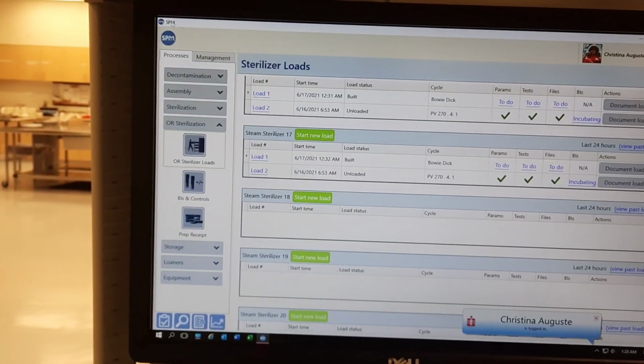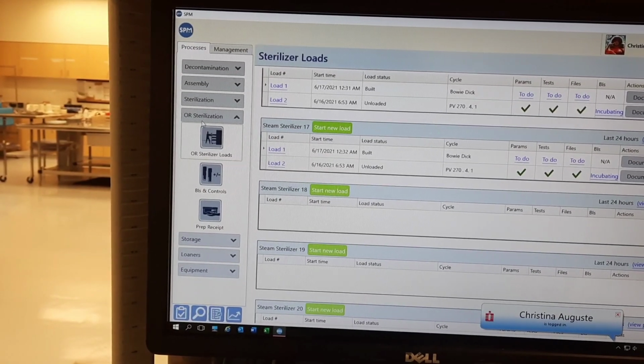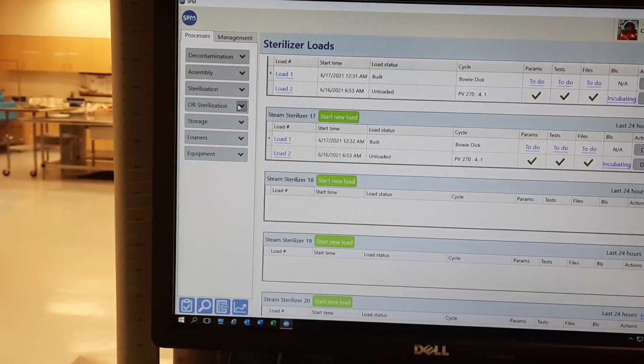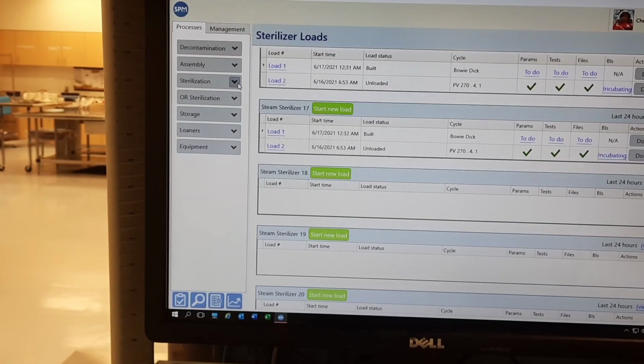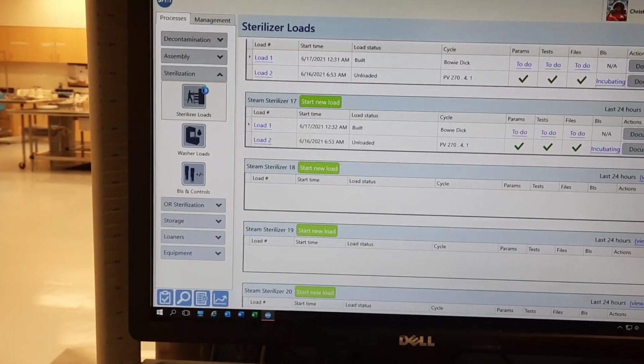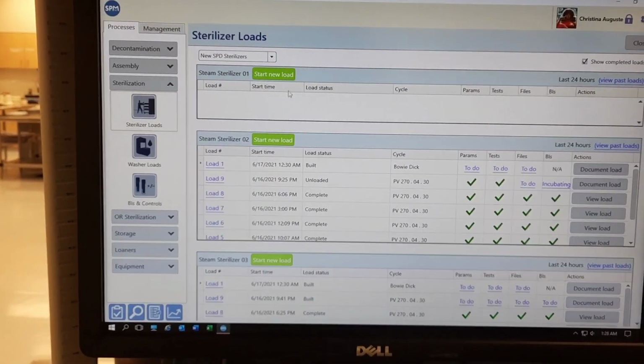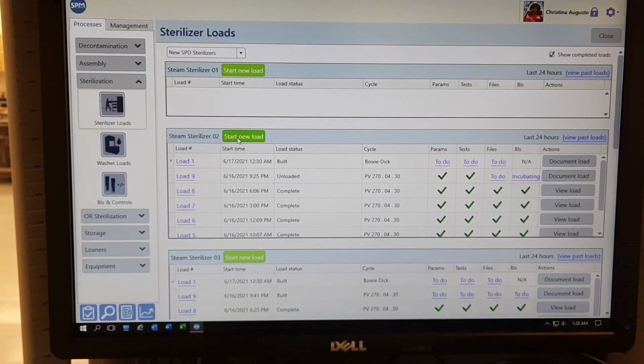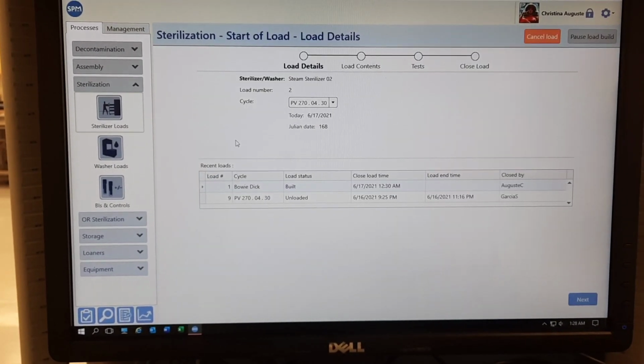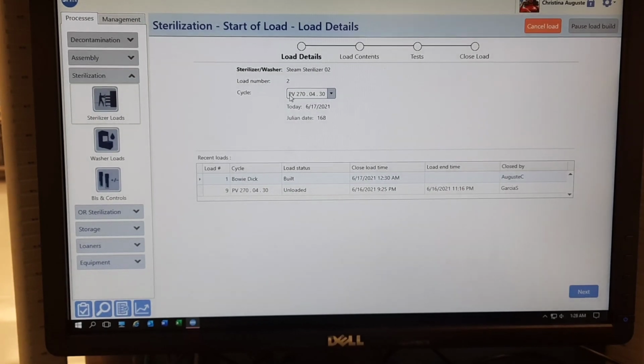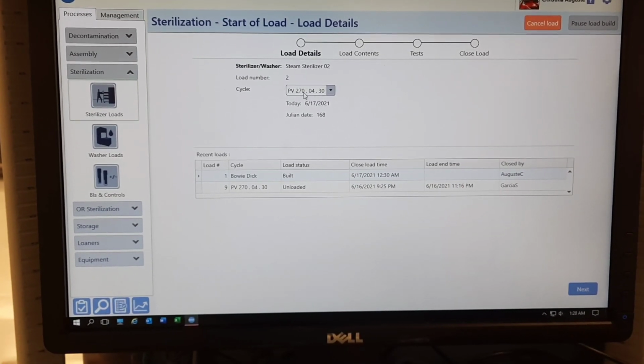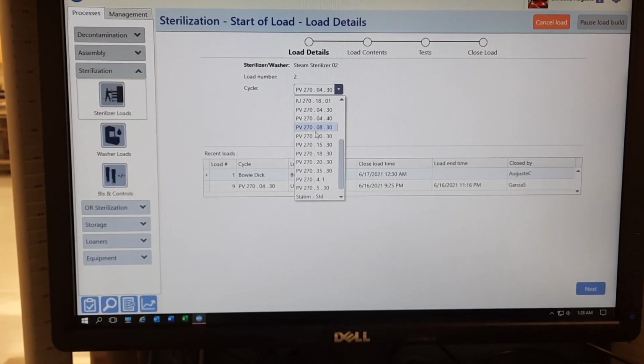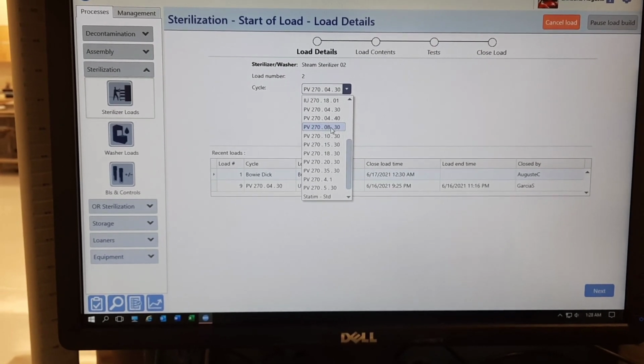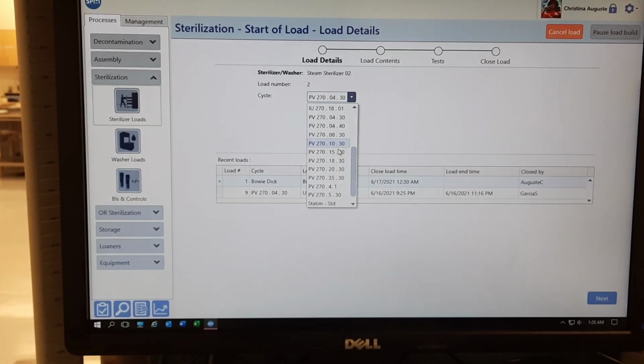So this is a tracking system. It's called SPM. And this is how you would load it. We'll start a new load. Pick the cycle. This is vacuum, pre-vac. And they have all different types: 8 minutes sterilization, 10 minute sterilization. And I shouldn't explain what sterilization means.